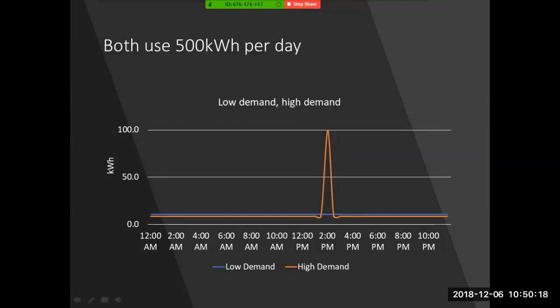So I'm going to skip to this graph here because it's fairly easy to get confused between use and demand, and they are two very different things. For both of these graphs, both are using exactly 500 kilowatt hours per day. As you can see, the orange graph, it's all the area underneath, so on average it's slightly lower than the blue one, and the blue one's perfectly straight all the way across. Now, although they both use 500 kilowatt hours per day, the demand for the orange graph is roughly 10 times higher than the demand for the blue line.